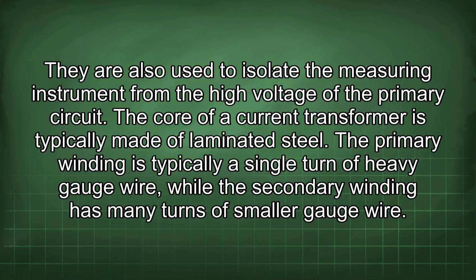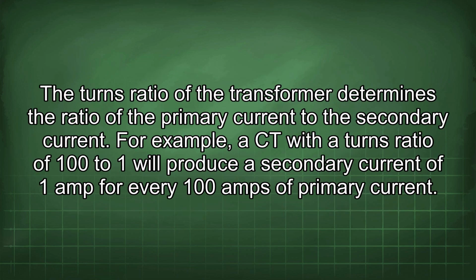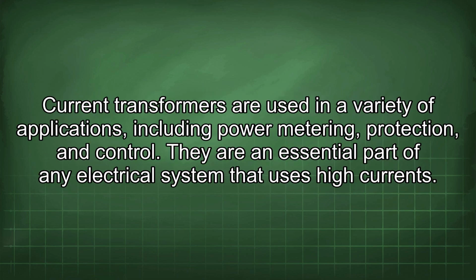The core of a current transformer is typically made of laminated steel. The primary winding is typically a single turn of heavy gauge wire, while the secondary winding has many turns of smaller gauge wire. The turns ratio of the transformer determines the ratio of the primary current to the secondary current. For example, a CT with a turns ratio of 100:1 will produce a secondary current of 1 amp for every 100 amps of primary current. Current transformers are used in a variety of applications, including power metering, protection, and control. They are an essential part of any electrical system that uses high currents.